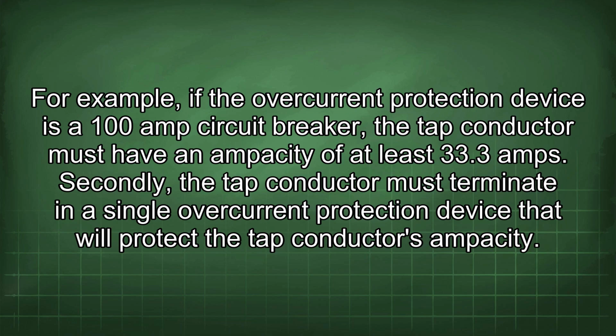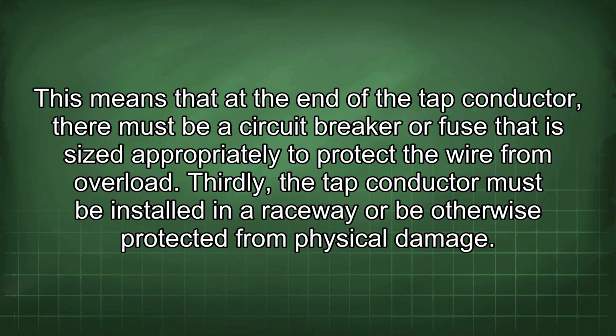Secondly, the tap conductor must terminate in a single overcurrent protection device that will protect the tap conductor's ampacity. This means that at the end of the tap conductor, there must be a circuit breaker or a fuse that is sized appropriately to protect the wire from overload.